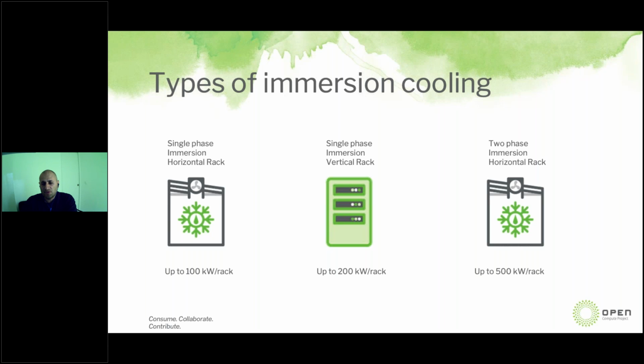And two-phase immersion horizontal rack: energy transferred from the servers into the fluid causes a portion to boil off into a gas, and the rising vapor condenses on a water-cooled condenser. The coolant changes phase, providing higher heat transfer with extremely higher density.